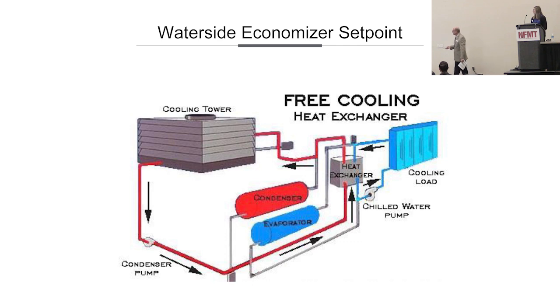By the way, it's worth a side mention on this one, because that turned into one of those symptoms that we now see on cooling towers. One of the first questions now is, what the heck is the basin hot or the basin cold water thermostat set at compared to what the desired economizer rule is. But one of the other places we saw an interesting challenge, and we put it out there as kind of the asterisk to the story.